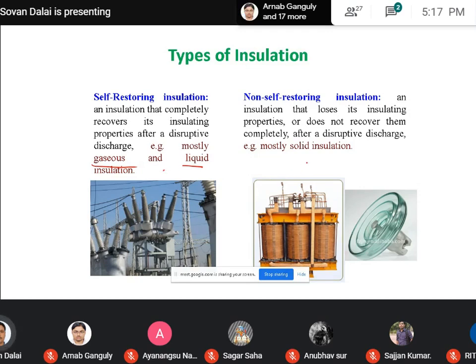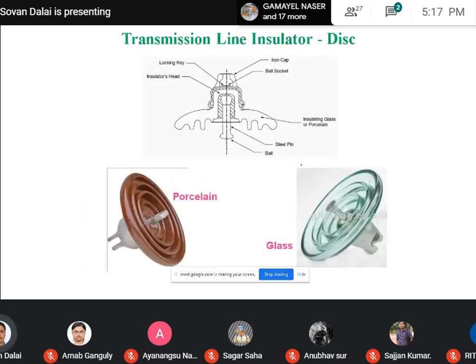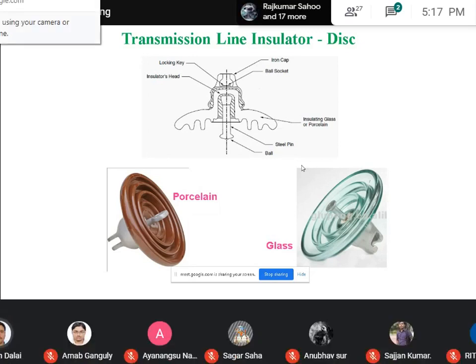And in the case of non-self-restoring insulation, if it is damaged, it can't regain its insulating properties. Most of the solid insulation is of that nature. As a transmission line insulator, I already mentioned that the air surrounding the conductor acts as an insulator, but to isolate the conductor from the transmission line tower, we use different types of insulator. That is basically the solid insulator, made either of porcelain or of glass. These are basically called disc insulators.